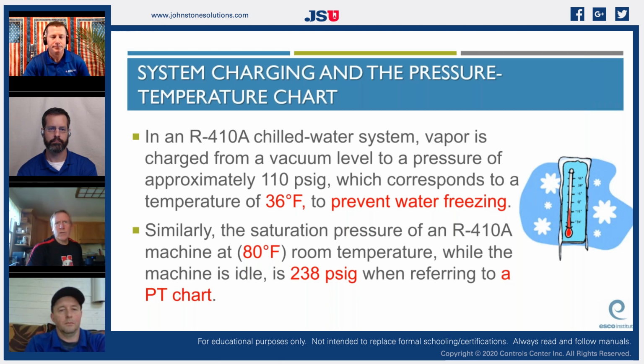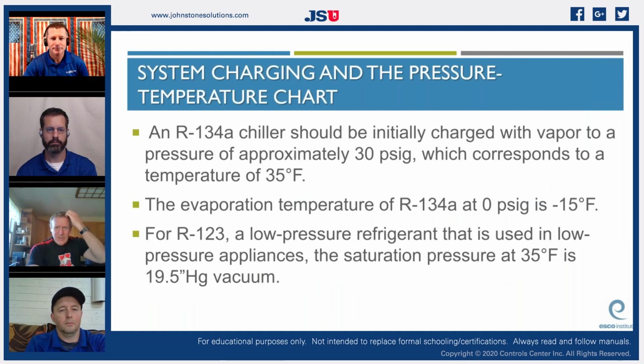And it's a good thing to know because we've had a couple incidences here where the technician thought that another company put the wrong refrigerant in the system. Right. By the color of the drum the homeowner described, by the way. So I said, has it been off for a while? And he goes, yeah. And I said, take an accurate temperature, put your gauge on it, and see what the heck it reads. If it's 410A at 80 degrees, it's going to be 238 or right around there. If it's 22, it's going to be around 144, by the way. There's almost 100 pounds difference. If it's 170, you probably got an issue. That's right. So just a good way to use a pressure temperature chart to get you out of some trouble.